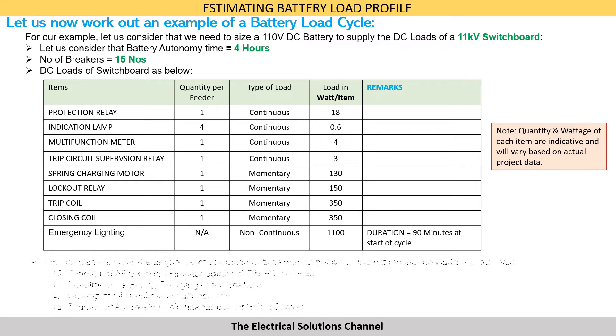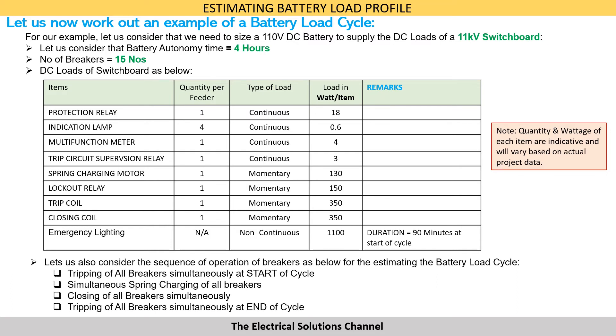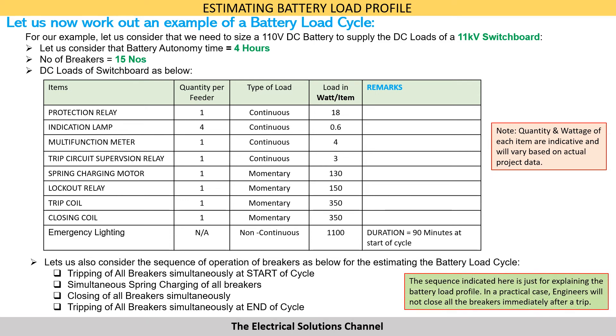Let us consider the sequence of operation of the breakers for estimating the battery load cycle. We will consider tripping of all breakers simultaneously at the start of the cycle, followed by simultaneous spring charging of all the breakers, then closing of all breakers simultaneously, and finally tripping of all breakers simultaneously at the end of the cycle.